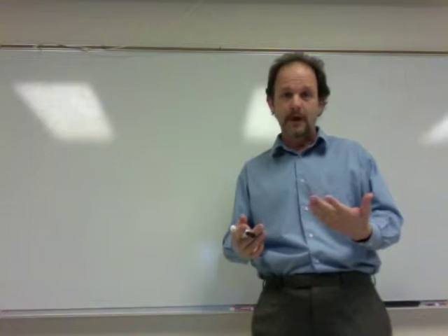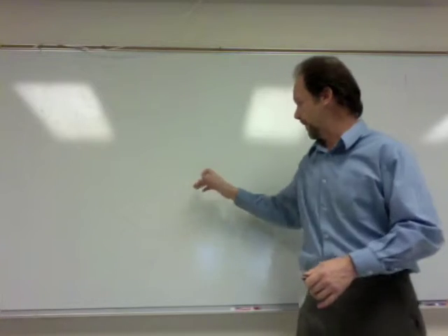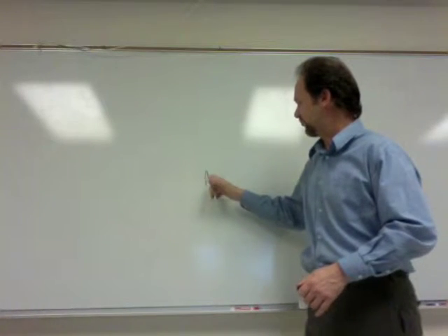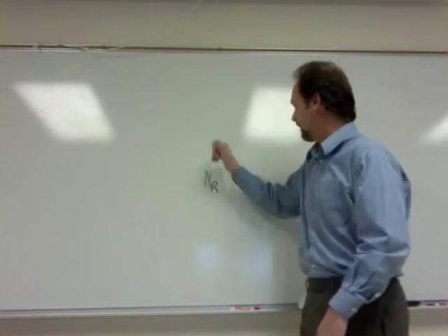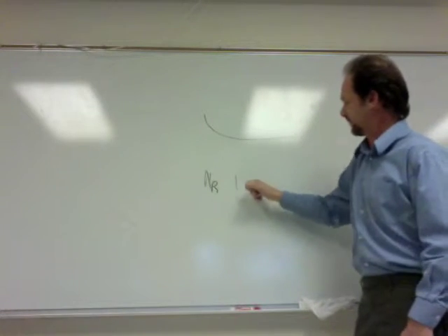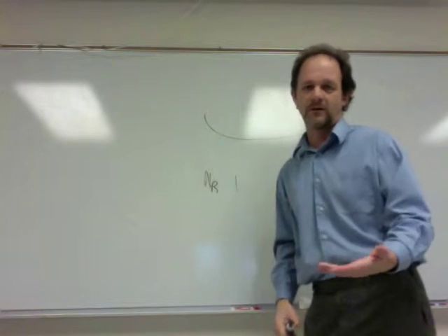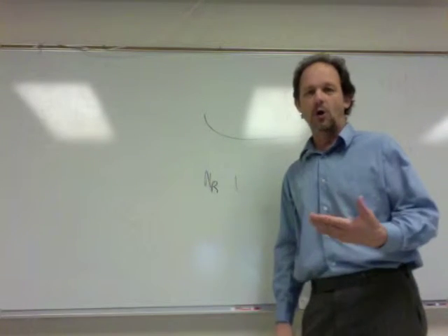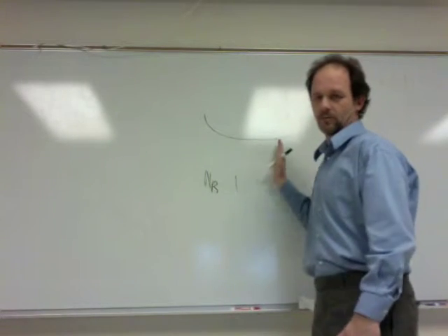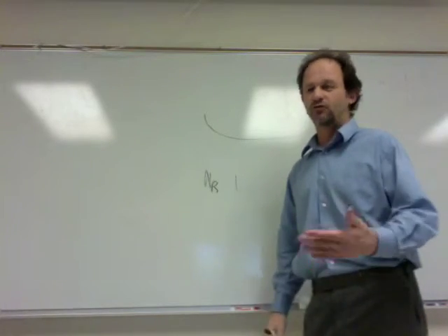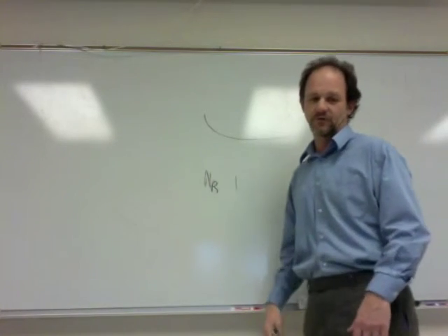Now, it will come out with a Reynolds number, N sub r, and you should check that again in your Moody diagram to make sure that that Reynolds number is in the flat section, because this is an iterative process. Though in all reality, if you're in a pretty fast-moving system, you should be able to guess the friction factor the first time.